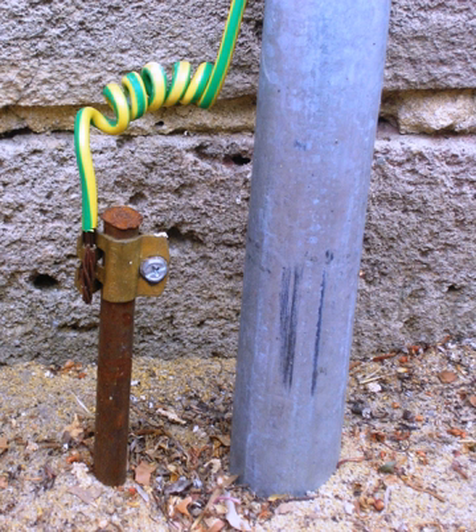Topic: Functional grounds. Some devices require a connection to the mass of earth to function correctly, as distinct from any purely protective role. Such a connection is known as a functional earth. For example, some long-wavelength antenna structures require a functional earth connection, which generally should not be indiscriminately connected to the supply protective earth, as the introduction of transmitted radio frequencies into the electrical distribution network is both illegal and potentially dangerous. Because of this separation, a purely functional ground should not normally be relied upon to perform a protective function.